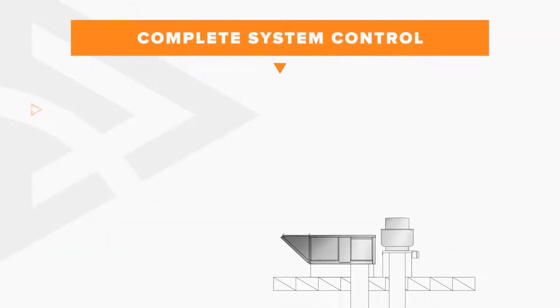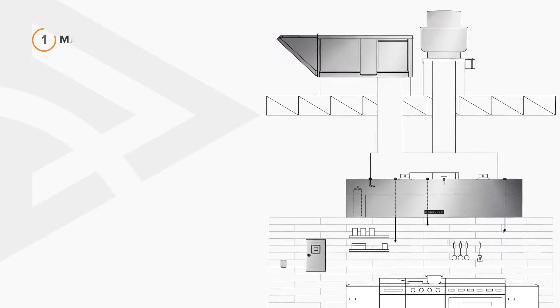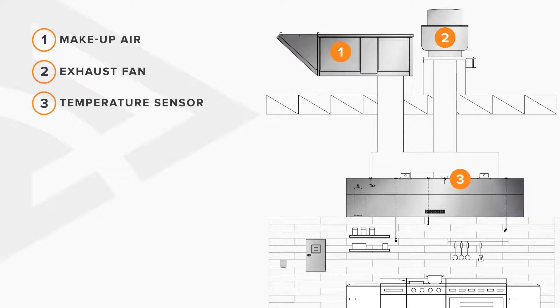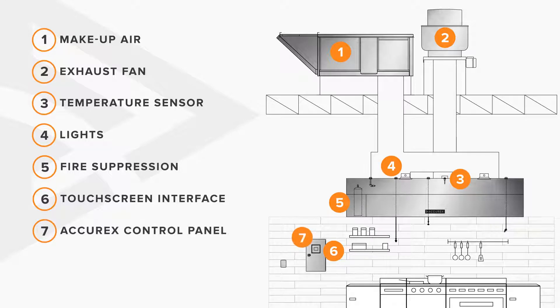Accurex controls provides complete control of all components of a constant volume or demand controlled kitchen ventilation system. Simultaneously control up to eight exhaust and make-up air units, tracking cooking loads through hood-mounted temperature sensors. Manage hood lighting and monitor the status of the linked fire suppression system, all controlled through the touchscreen interface of the remote or cabinet-mounted control package.